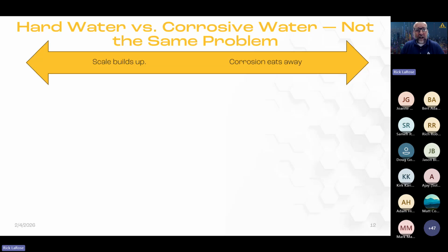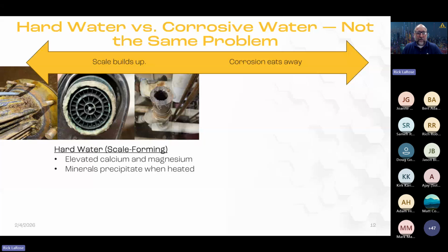The next thing I want to level set before we get into the generator itself is to help you understand the difference between hard water and corrosive water. Hard water is scale forming - those elevated levels of calcium and magnesium, and when we heat that water up, those minerals come out of solution and build up, they plate out, they stick to surfaces.